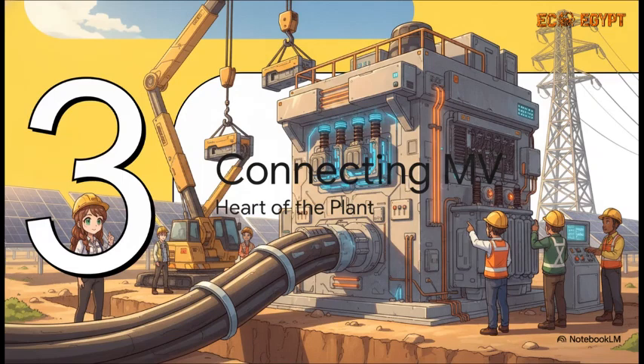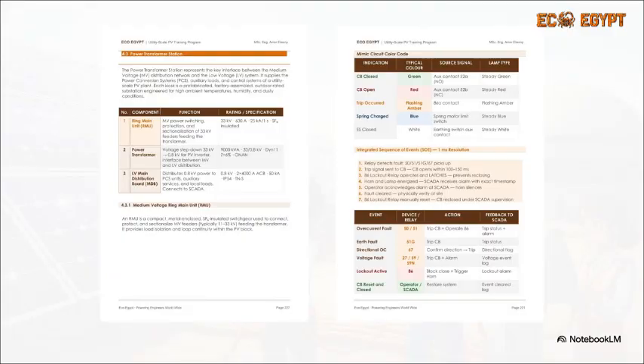On to Section 3, connecting the MV infrastructure, the true heart of the plant. All right, so our massive cable network is mathematically sized and safely buried in the dirt. Now it's time to connect the heavy machinery that actually steps the power up for the grid. Looking at these specs, our power transformer kiosks take the AC/LV, usually around 0.8 kilovolts, and dramatically step it up to a 33 kilovolt MV output.